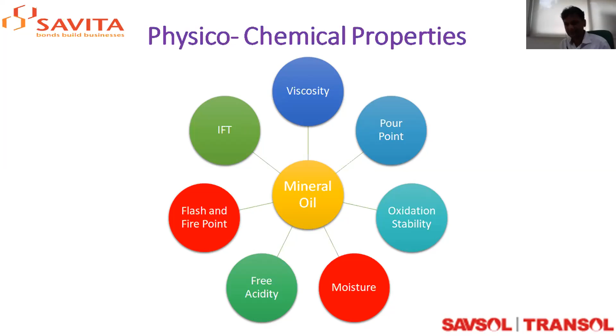Next slide. In terms of physicochemical properties of a fresh oil, there are 6 to 7 properties one has to keep a tab on: viscosity, pour point, oxidation stability, moisture, free acidity, flash and fire point, and IFT. As you know, these properties, when you take a fresh oil, have certain specifications as per IS 335 or certain international specifications, giving limited values, maximum or minimum, as given in the standards. We'll touch on each property and how its increase or decrease, if it goes above or below specification, is going to impact the electrical behavior or performance of the transformer.